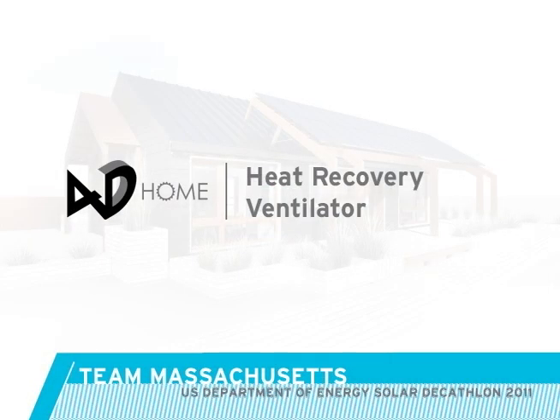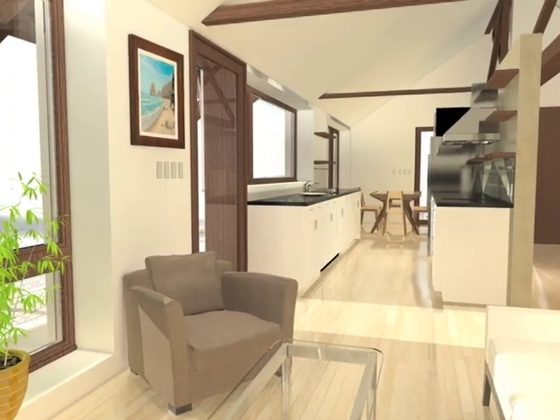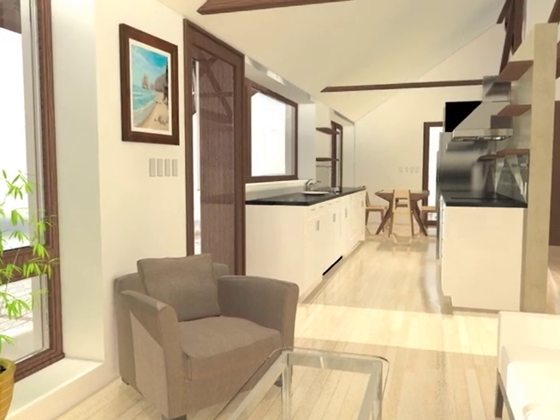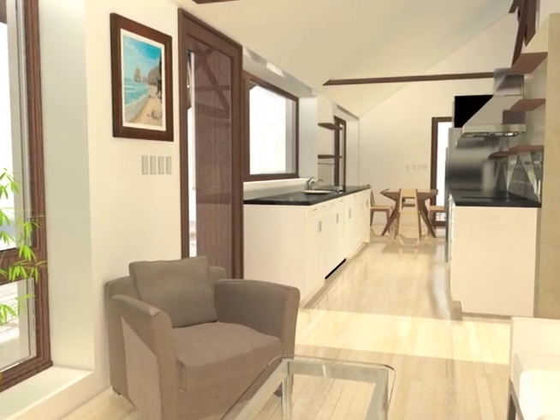A heat recovery ventilator is used to recover heat during ventilation. When fresh air needs to be brought into the home, the HRV uses the outgoing indoor air to preheat or cool the incoming fresh air. The heat exchanger in the HRV has an energy transfer efficiency of about 85%. The recovered heat directly supplements the home's heating load.